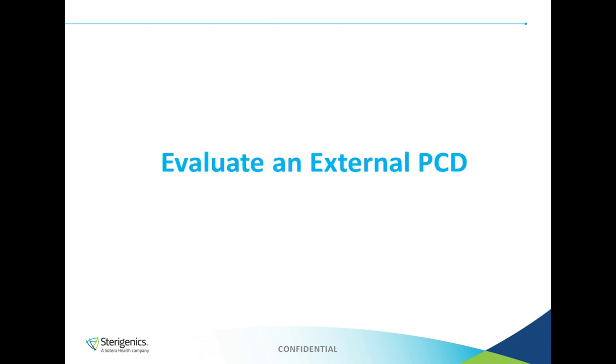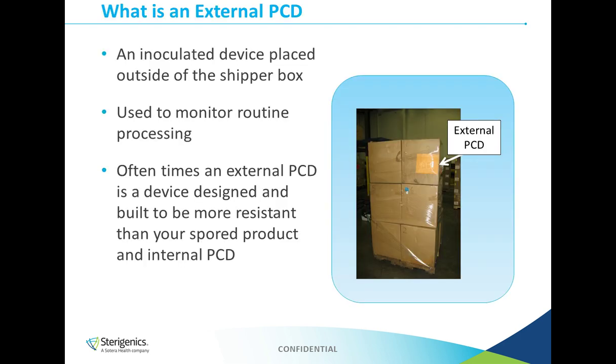So now we've talked about that internal PCD, we've confirmed BI appropriateness, and now the internal PCD has become your master PCD. We'll move on to the third objective, which is to evaluate an external PCD. Now an external PCD is an inoculated device that's actually placed on the outside of the shipper box. This is different than the internal PCD that is actually placed inside with the product. Now this external PCD is used to monitor routine processing.